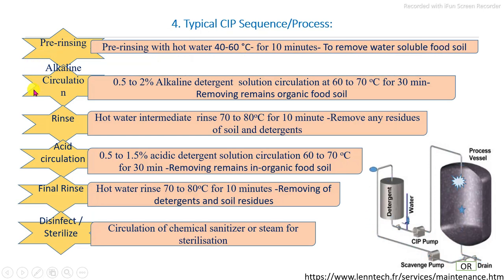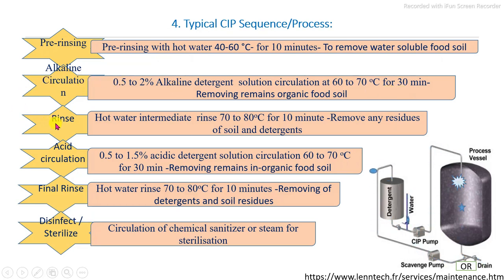The next step after pre-rinsing is the alkaline cleaning process using caustic soda solution at 0.5 to 2 percent concentration, at 60 to 70 degrees Celsius, circulated continuously for 30 minutes to remove remaining organic soils present on the internal processing line. After that, an intermediate rinsing with hot water at 70 to 80 degrees Celsius for 10 minutes removes residual food soils.